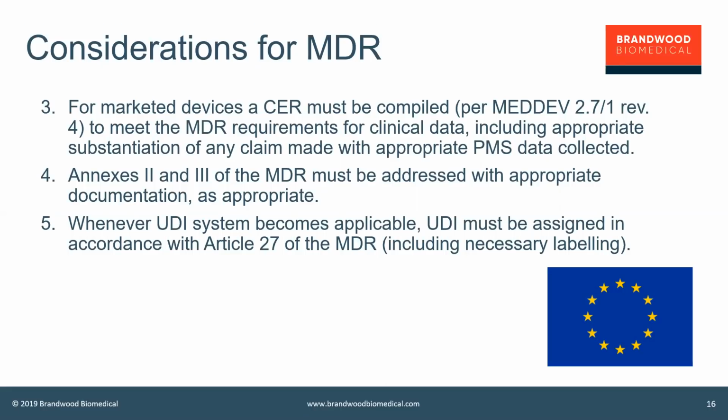Now, it's not going to change whether you have a requirement for clinical data. Unless you're up-classified where there's an expectation that direct clinical data on your device is needed, the CER is still the way to establish your safety and effectiveness profile by using, one, comparative devices, having those equivalent devices and using their post-market history, their publications to support your device.